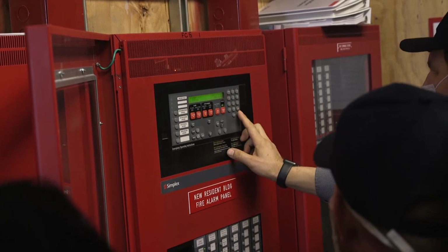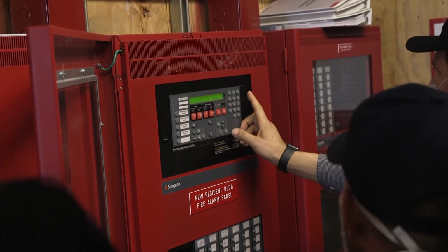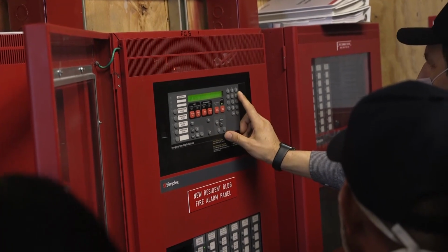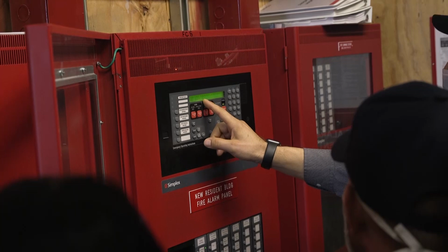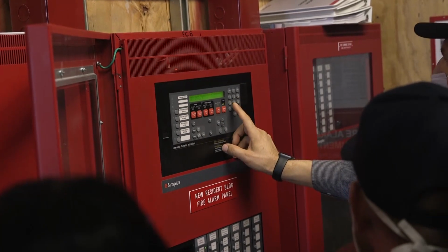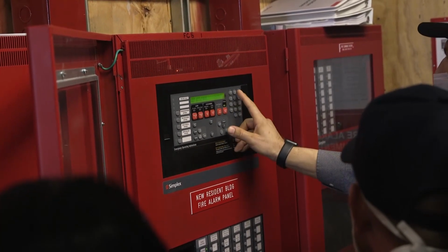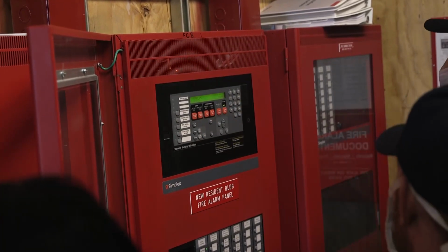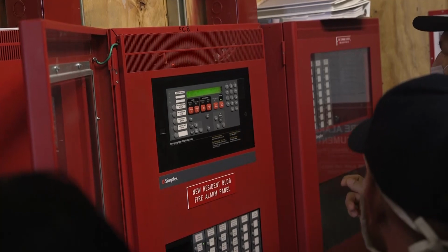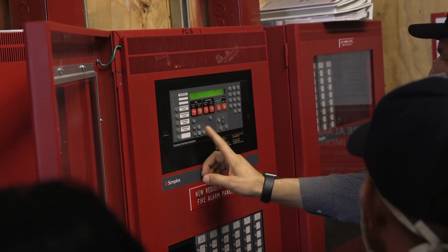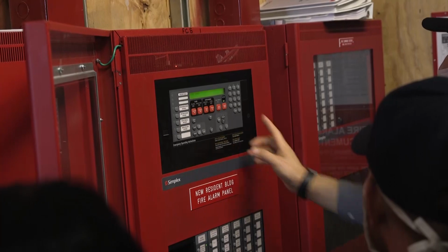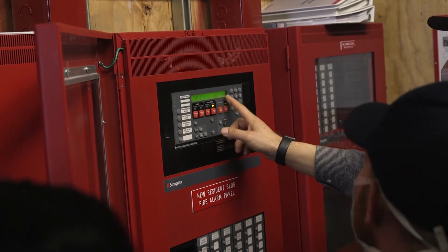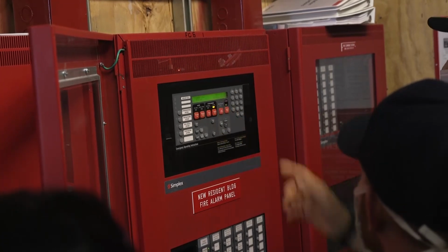That was 7-31, all right? To call that number, you press IDNet, which comes up as M7-31. Enter, and you get this pull station on the screen. Now you can disable or enable. To disable, you press disable, enter. The pull station is disabled and comes up as a trouble: 7-31 disabled trouble.